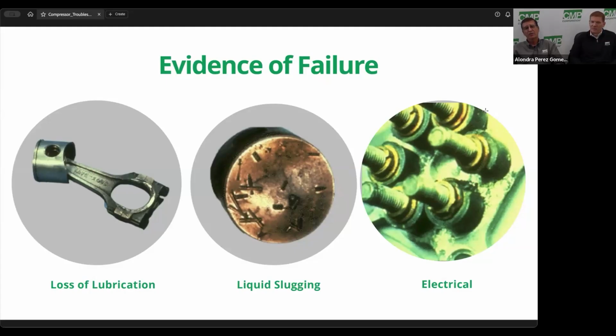And it breaks parts. Like I said, you're trying to compress a liquid when it enters that cylinder, and it can't get out the discharge holes fast enough. It's going to break the parts. It's going to blow gaskets or break a valve reed or break a rod. And the way we can tell is because we take it apart, and the rod's just as shiny as it can be. The surfaces of the rods are fine. The skirts on the pistons are fine. And everything else inside the compressor is fine except for the broken parts. They're not scuffed or galled from lack of lubrication because it had oil. It just can't swallow that liquid.